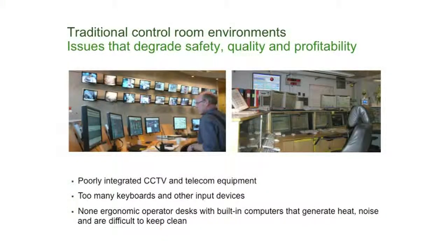Poorly integrated CCTV and telecom equipment is also a big issue in many control rooms. I've seen a lot of different solutions and ways to work around this. This left picture here is from a waste-to-energy plant in Denmark, which is a fairly new installation. It looks kind of impressive when you walk into that control room and you see all those TV monitors up there on the wall. But think about it, the operator, he's got a different angle into his process. That's what he is responsible for. Anything could go on those screens up there and he would have absolutely no way to identify that.